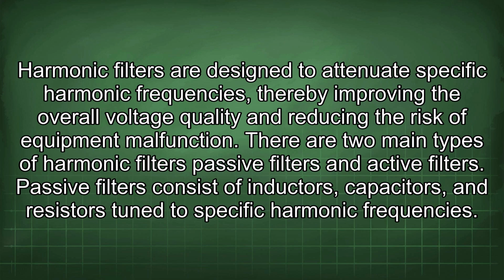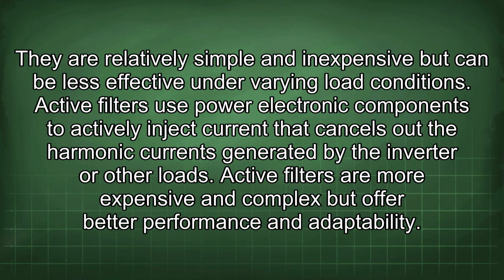Passive filters consist of inductors, capacitors, and resistors tuned to specific harmonic frequencies. They are relatively simple and inexpensive, but can be less effective under varying load conditions. Active filters use power electronic components to actively inject current that cancels out the harmonic currents generated by the inverter or other loads. Active filters are more expensive and complex but offer better performance and adaptability.